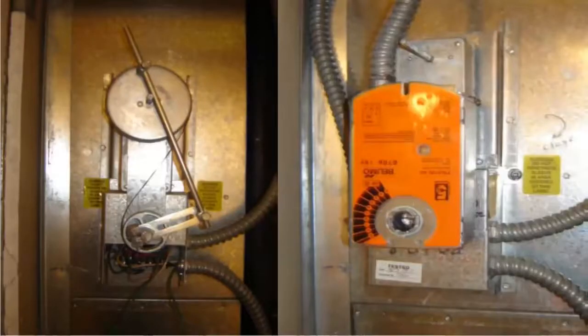Next. So here's a typical example: on the left side, old motor, old damper, a lot of stuff. You can't replace that motor. That's not made anymore. But you can tear everything off and go straight for the damper shaft. You add a coupler and a new actuator. You've actually turned it into a modern damper by using the method on the right. This happened to be a job with a 100% defective rate. There were only 22 of them, but every motor in the place was bad, and the dampers were all screwed open, held by a screw. Next.